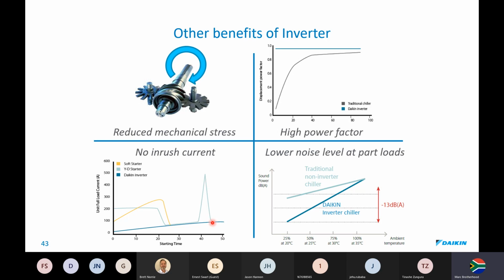You could get any kinds of spikes. However, on an inverter, it's linear. We probably start at 20 amps and we go right up to the running current. You'll notice all of these are also as back EMFs kick in, the starting current drops right down to your running amps. We also have low noise levels at part loads because we commutate the rotational speed of the compressor.